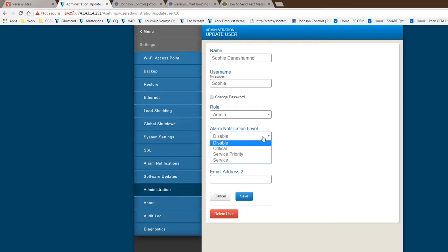After you have the internet connection, you can come in, add your users, and create the notification level that is needed. We have three notification levels: critical, service priority, and service. Critical, pretty self-explanatory, means all the critical alarms within the system. Things like smoke detection, things like shutdowns, things like high pressure trips, low pressure trips. Any of those becomes a critical fault.